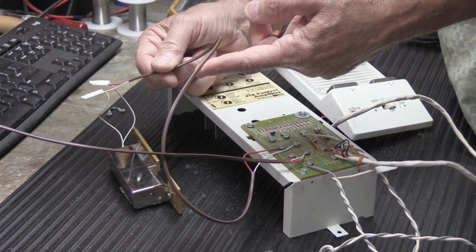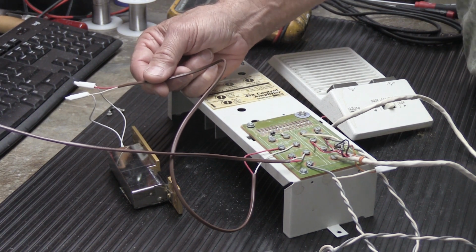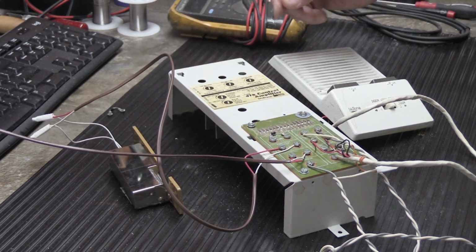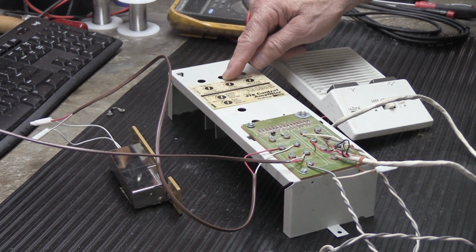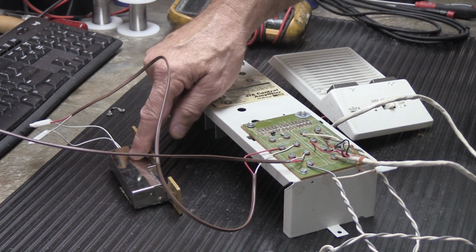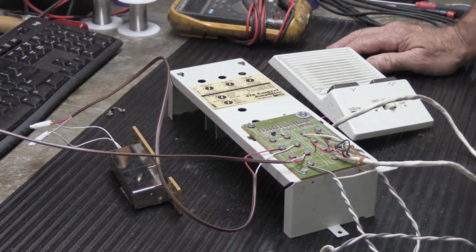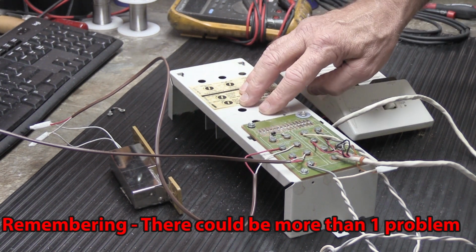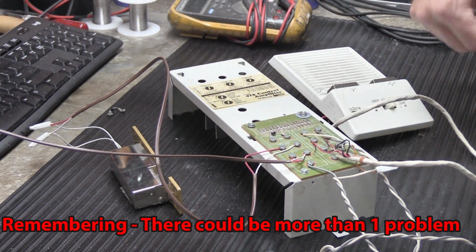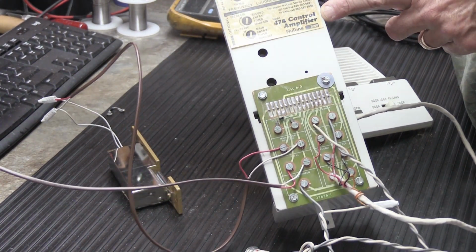Sometimes mice chew on wires, or things break loose or whatever, so you have to look at the wire. And then lastly, and actually most commonly, or maybe most commonly, it's probably a push either way, whether a door strike or the control amplifier would be the primary thing to look at first. But these control amplifiers can fail in regards to activating the door release. There's a reason why this is called a control amplifier.